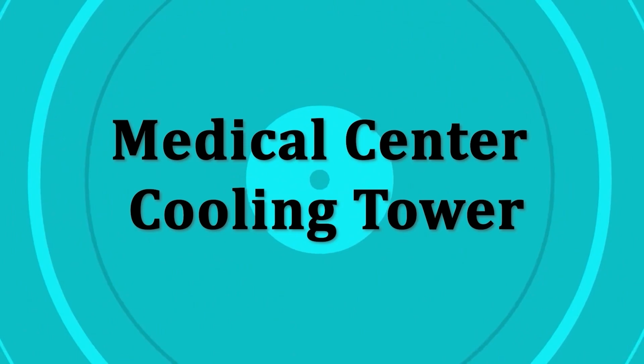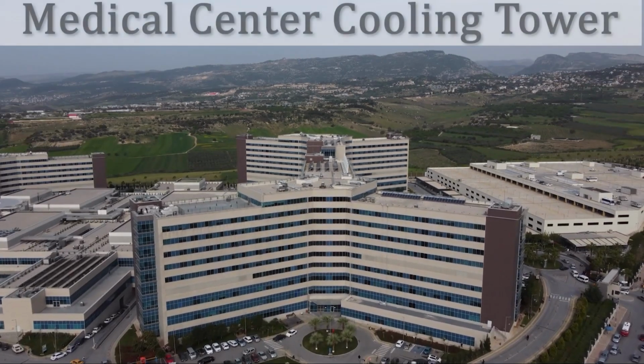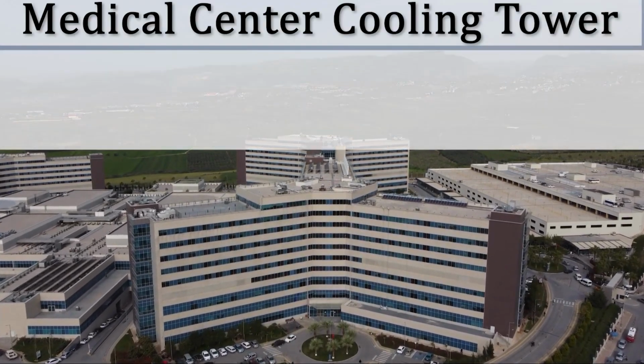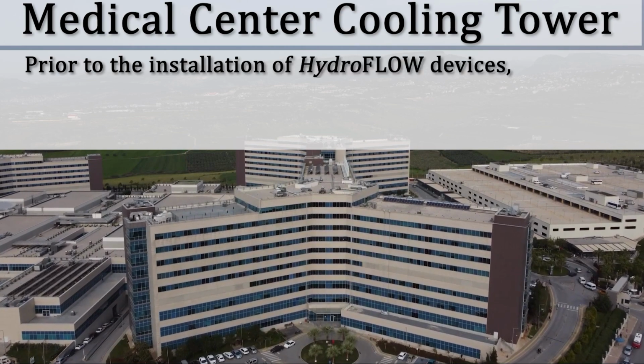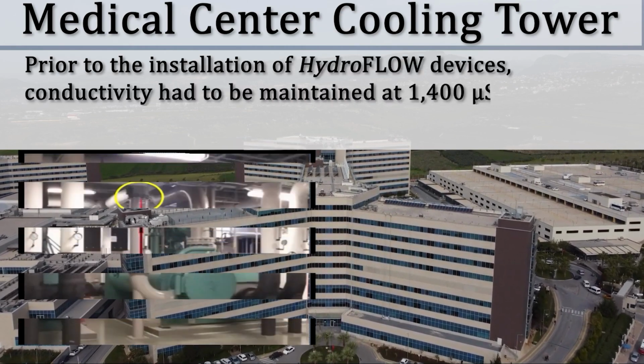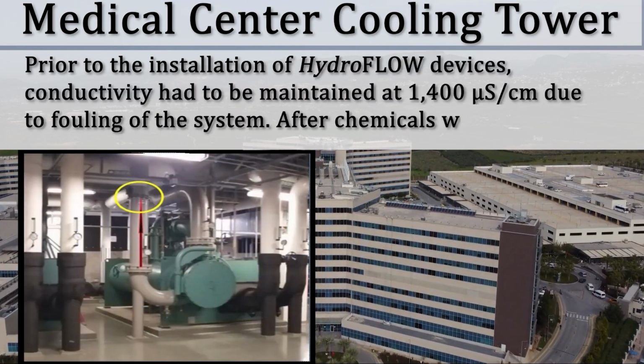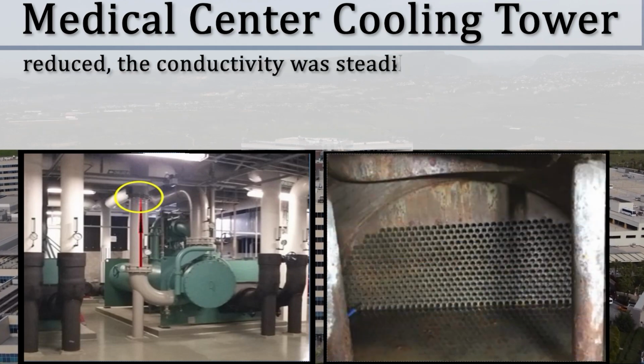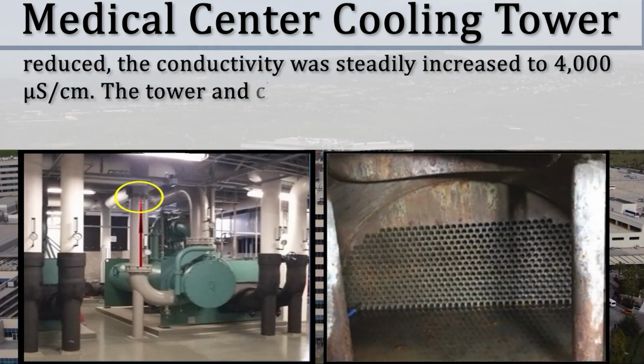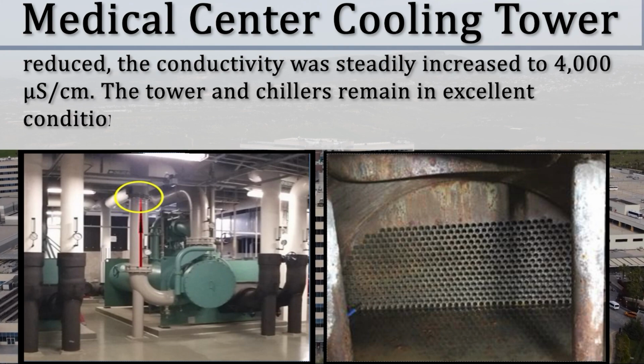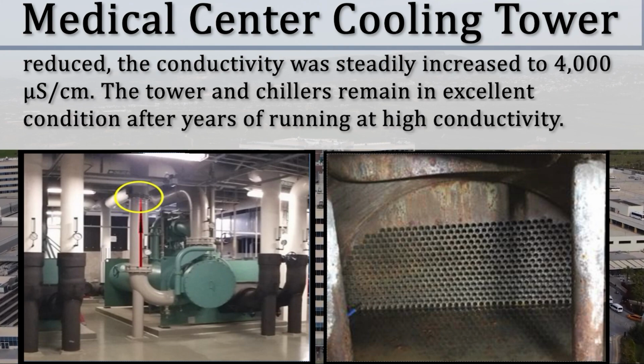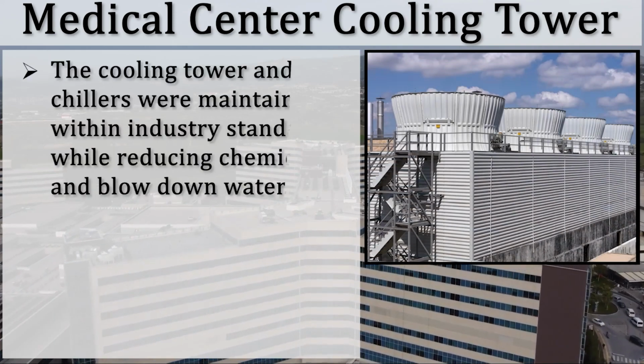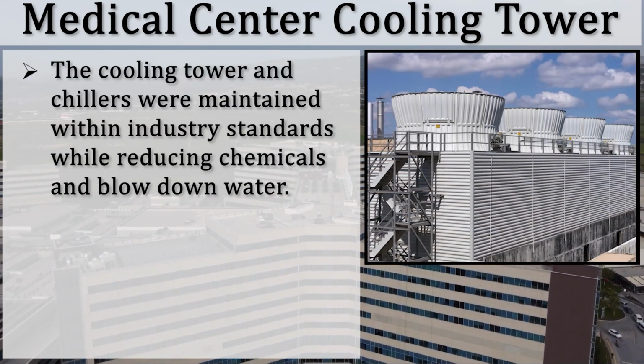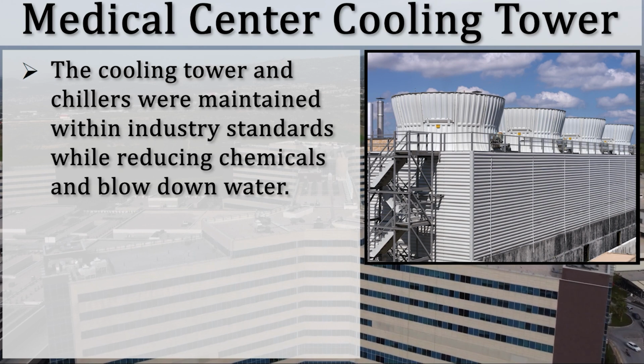Medical Center cooling tower. Prior to the installation of HydroFLOW devices, conductivity had to be maintained at 1400 microsiemens due to fouling of the system. After chemicals were reduced, the conductivity was steadily increased to 4000 microsiemens. The tower and chillers remain in excellent condition after years of running at high conductivity. Results: the cooling tower and chillers were maintained within industry standards while reducing chemicals and blowdown water.